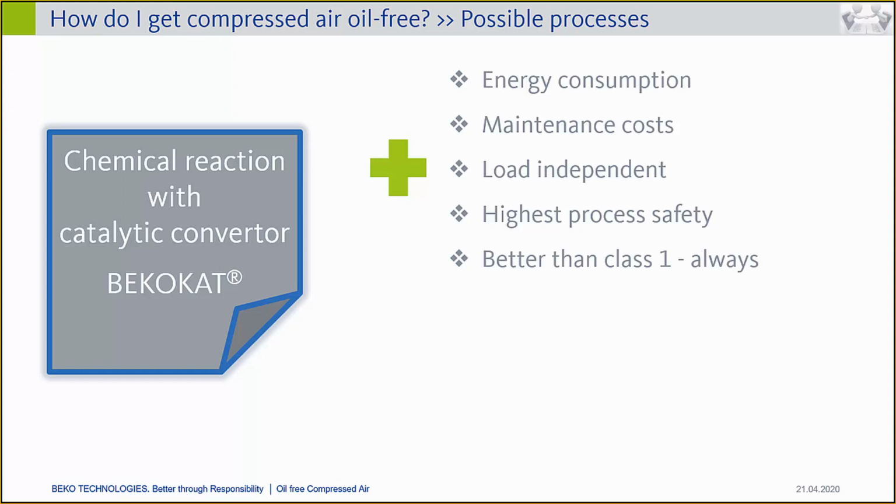We figured that out by measurement, and that is the result. So the time when the catalyst needs to be exchanged is quite long. In the new generation, we recommend about 5 years. That is totally different to a yearly exchange of activated carbon, for example.